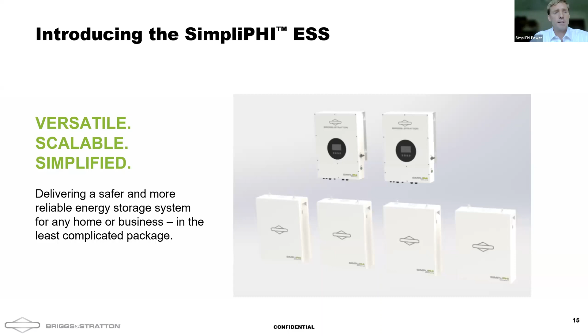Of course, like all lithium iron phosphate batteries, there are temperature considerations. These batteries cannot be charged in temperatures below freezing. So when the internal temperature of the battery is below freezing, they can't be charged. They can be discharged down to, I think, -4 Fahrenheit. So pretty cold temperatures, 32 is freezing, right? So pretty good cold temperatures they can discharge in. But that's a consideration if you're doing this in extreme cold environments. You might want to install these indoors or in an insulated cabinet, etc.